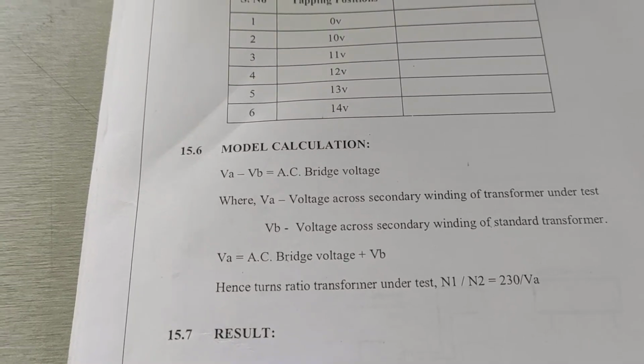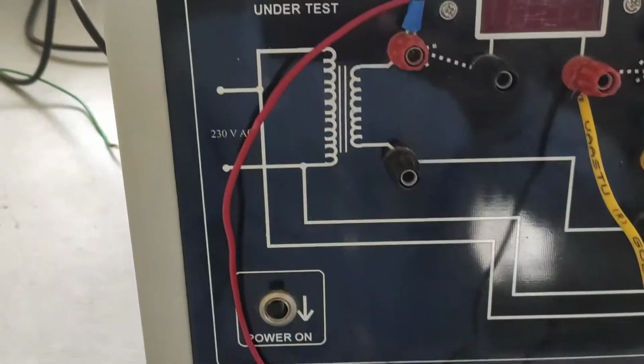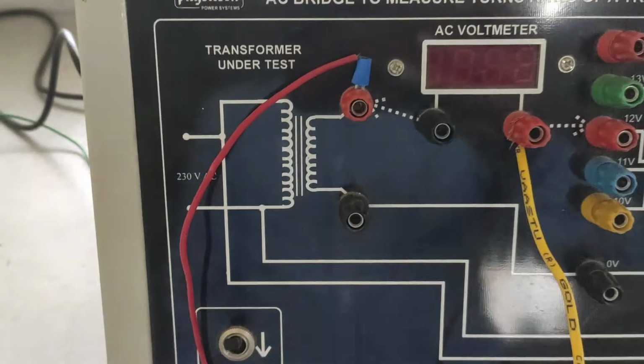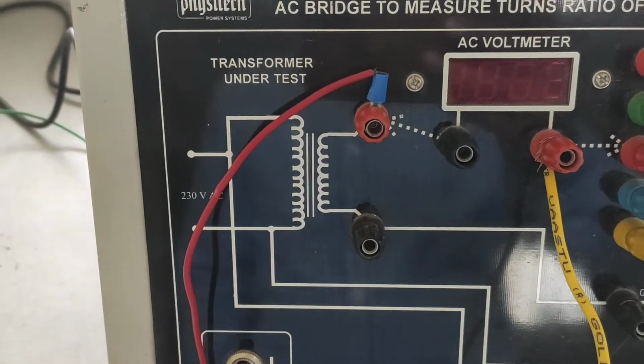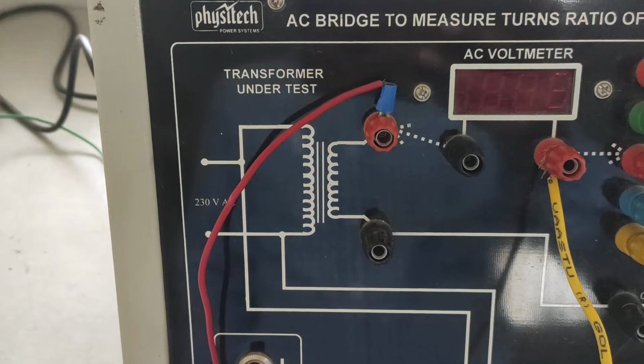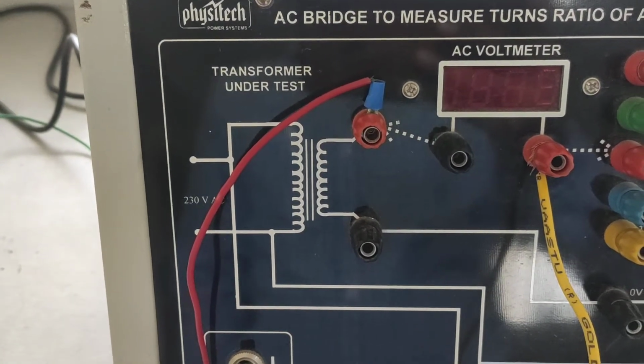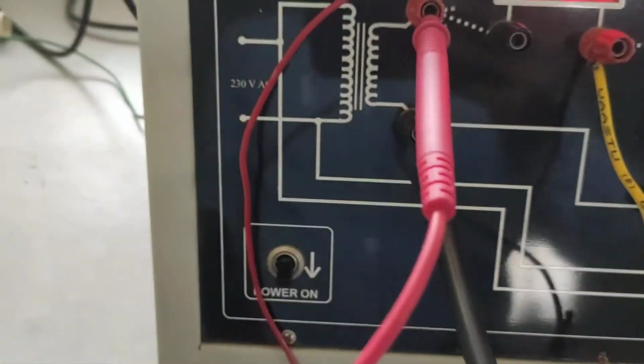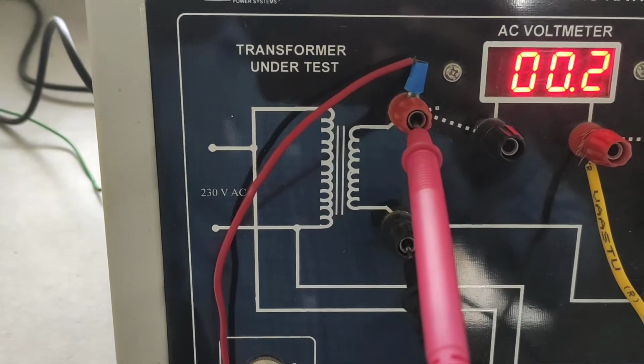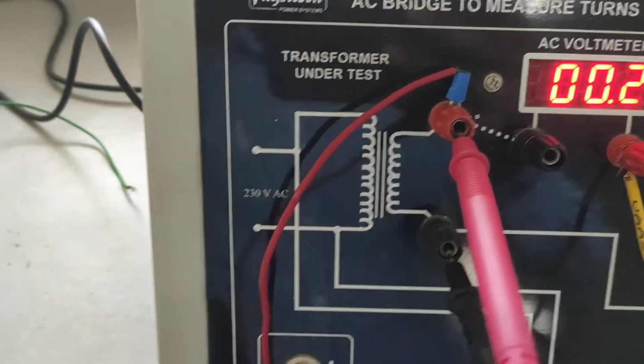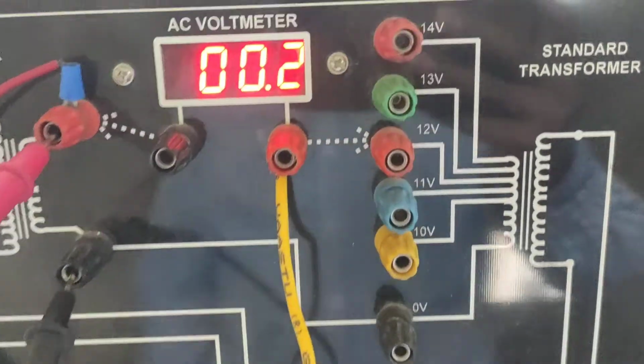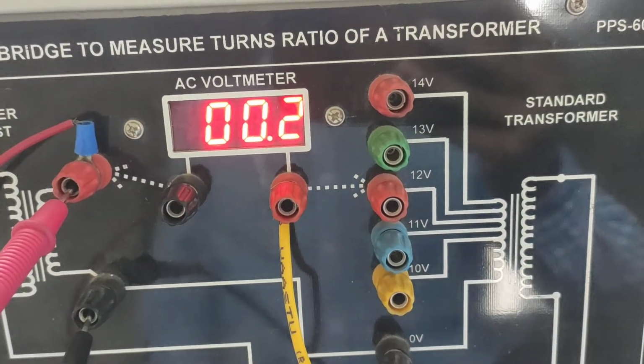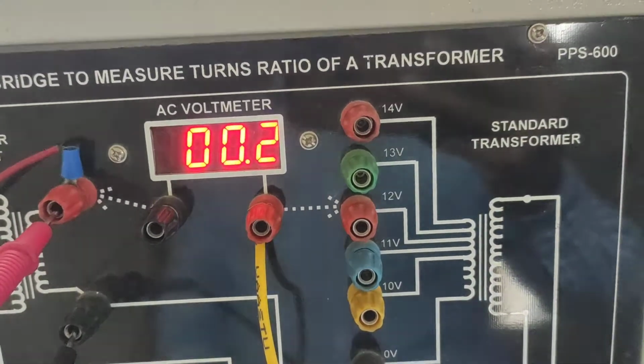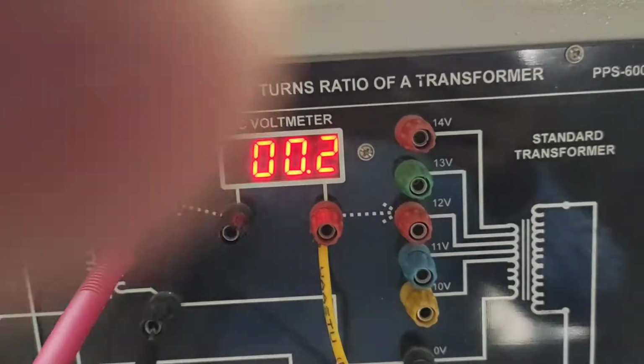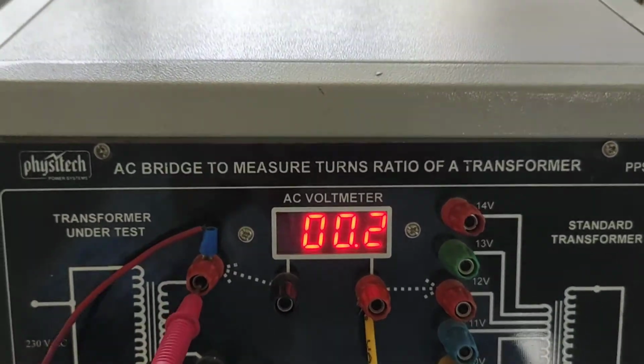As you know the VA voltage, for the transformer under test, by connecting a multimeter we can find the voltage across the terminals of the transformer. You can find it as 12 volts. Let me see how it is going to appear. If you check the secondary voltage of the transformer under test, it is a 230 to 12 volts transformer, and you can find the voltage is 12 volts. Now you can vary the tappings of this transformer. By varying the tappings of the transformer you can find the variation of the voltage. So we'll see the variation of the voltage with respect to these tappings like this.